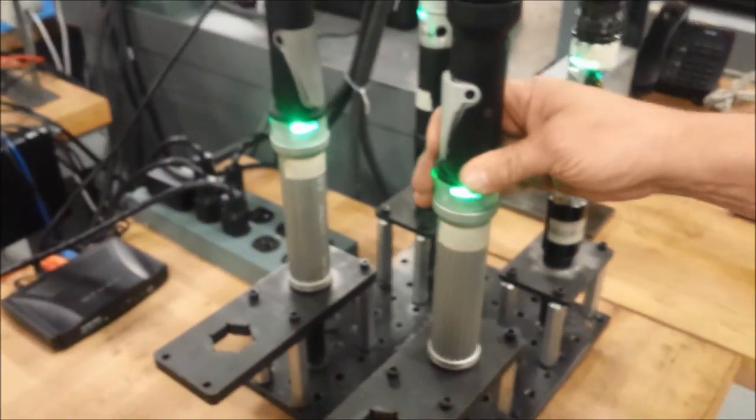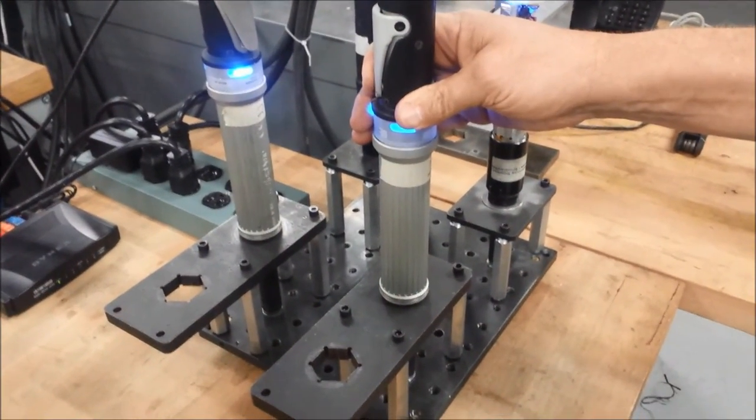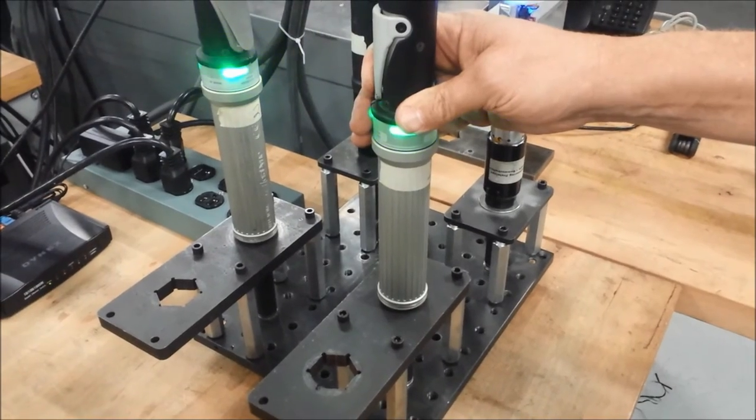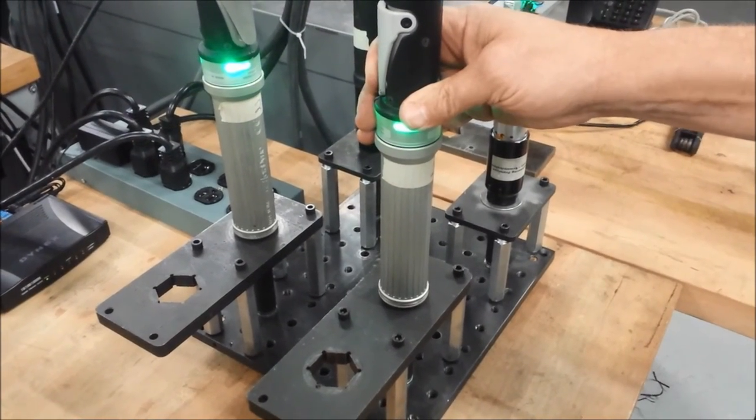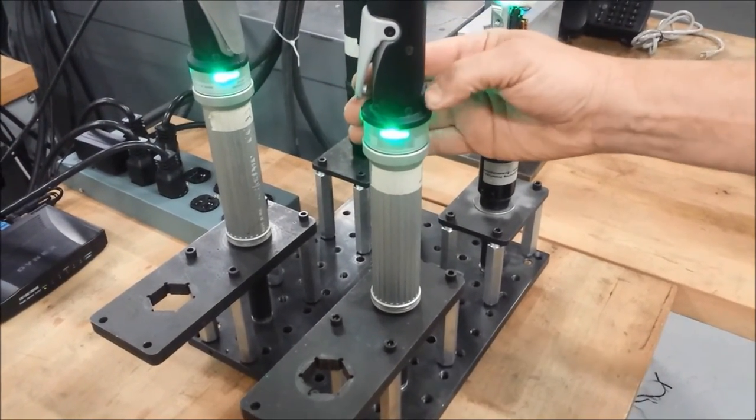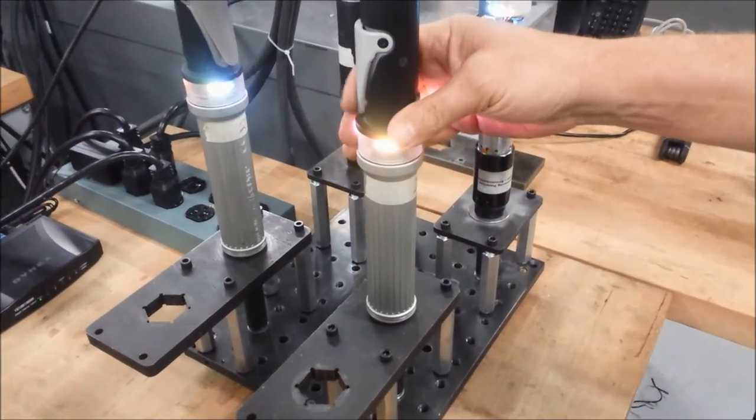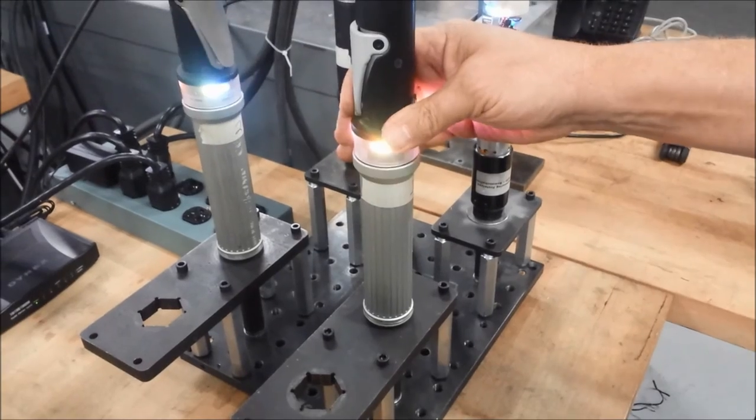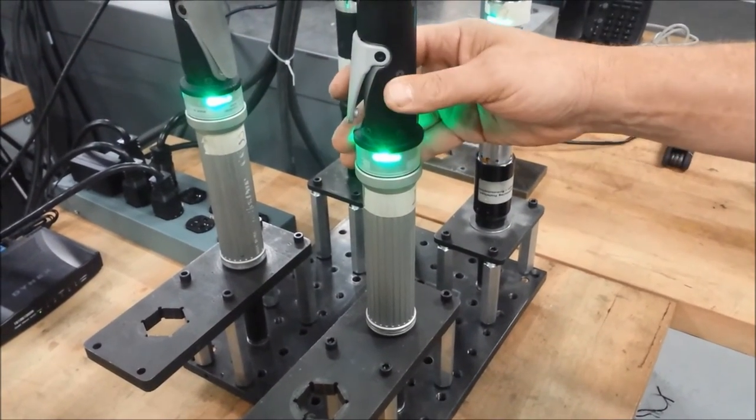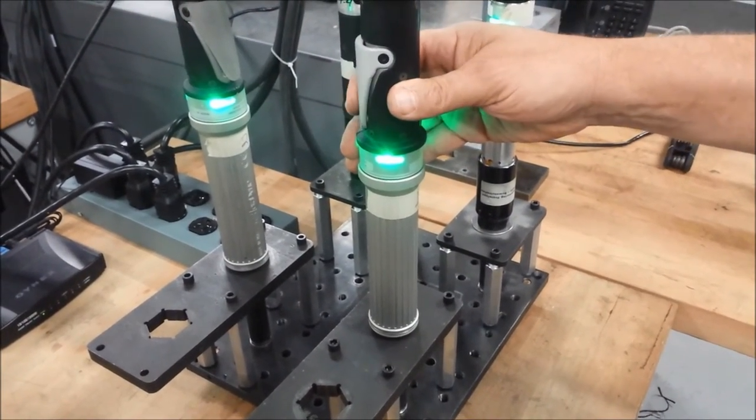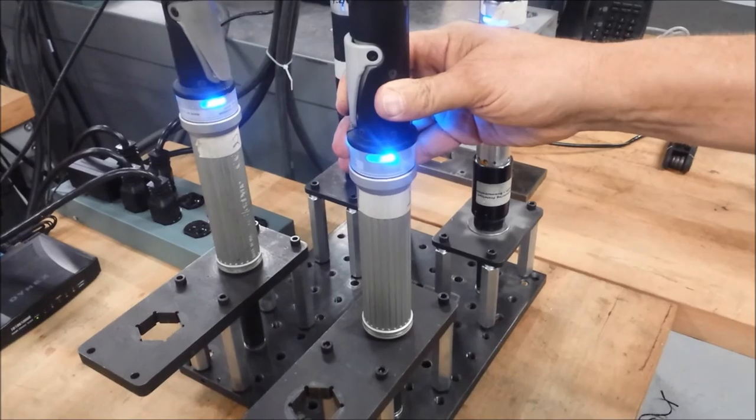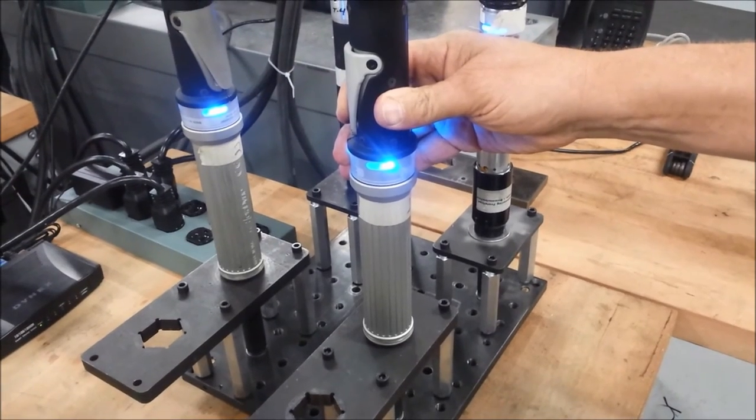Note we can employ sophisticated strategies. In this case, we are running the tools down, pausing for synchronization, reversing the tools 360 degrees, and then completing the torque sequence to 8 Nm, all controlled by the single master tool lever.